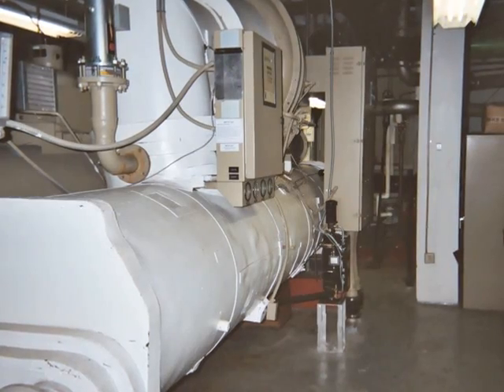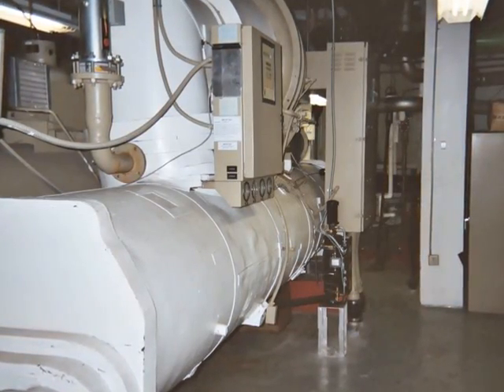On a type 2 scenario chiller, the OAM is still applicable since you have regular oil migration while you're running at full capacity and an increased oil migration during low load situations. Therefore, the OAM would be able to keep you at 0.5% oil instead of getting somewhere between 3 and 6, maybe 6 and 12% oil during that time period, thus still saving the customer or chiller owner a significant amount in energy savings. Operating scenario type 3 is the worst scenario of all.